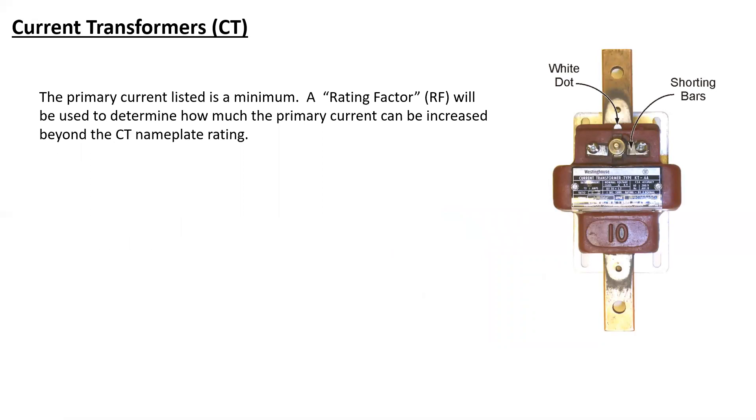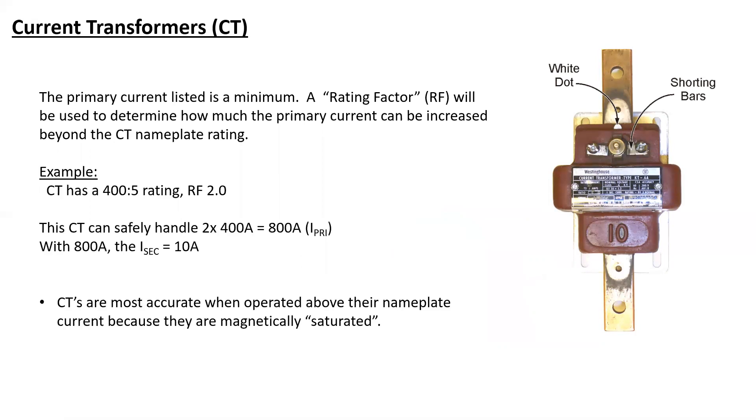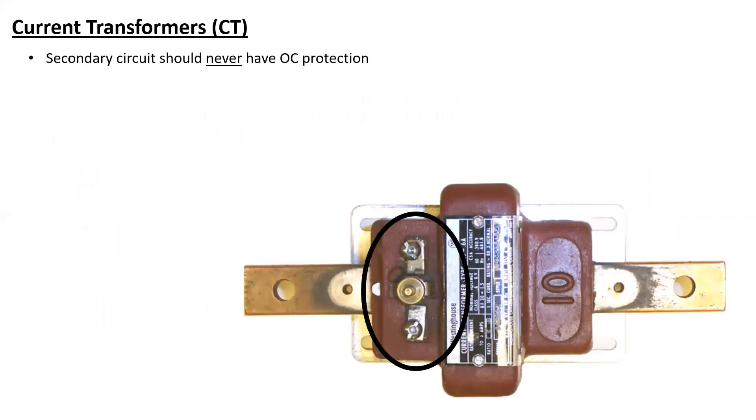On most CTs, what you're going to have is a rating factor. The rating factor is used to determine how much the primary current can be increased beyond the CT nameplate rating. So, the CT that we've been dealing with, 400 to 5, if it had a rating factor of 2, the rating factor is the item that is multiplied by the initial 400 amp rating. So, that means that that CT can safely handle 800 amps, 400 times 2. And with 800 amps, we would expect to get a secondary current of 10 amps. Interesting to note, CTs are most accurate when operated above their nameplate current because they are magnetically saturated. It means they're highly accurate and when we're doing revenue metering, we're charging someone for a product that has to be highly accurate in order to validate the billing.